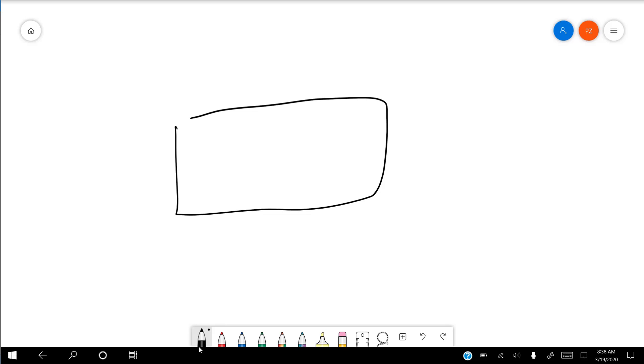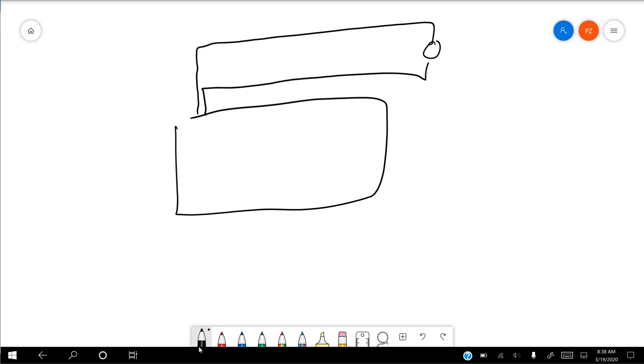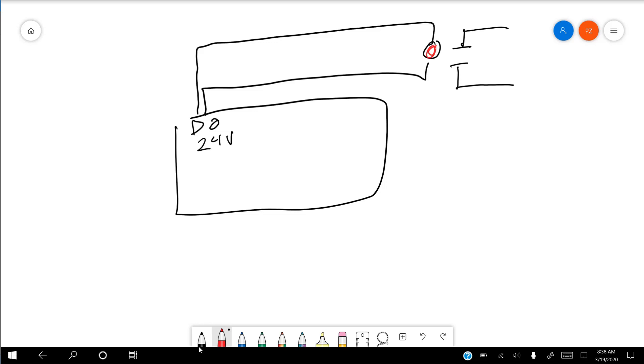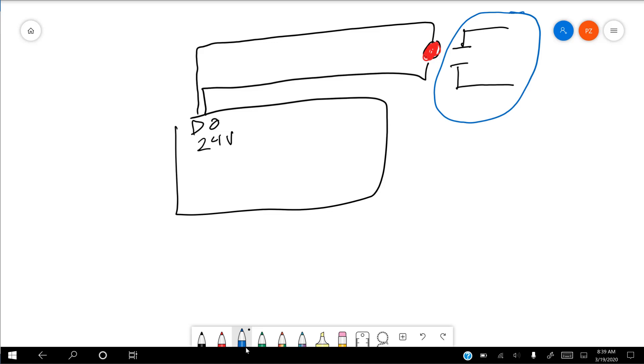What we do is turn on what is called a coil in order to energize a set of contacts. Our controller has a digital output and it's sourcing 24 volts — an internally sourced output — and it goes and energizes this coil. What the coil does is cause these contacts to change state. Right now the circuit shown in blue is a broken, open circuit, meaning electricity cannot complete the path.